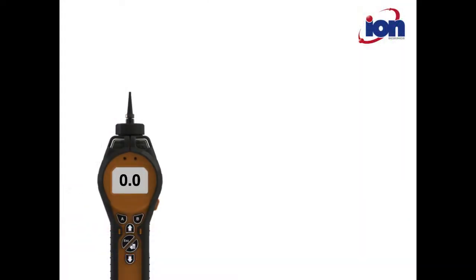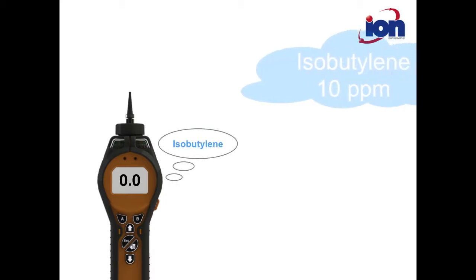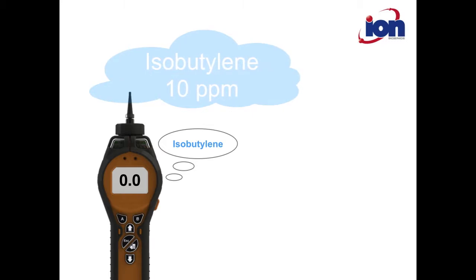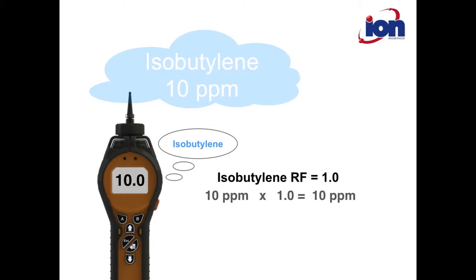This illustration shows an instrument calibrated on isobutylene. Isobutylene is also selected on the instrument, so the response factor used is one. The reading is therefore correct.